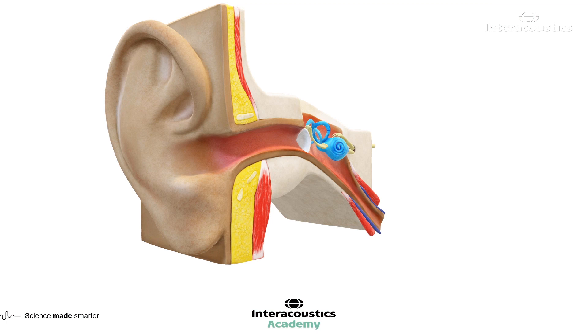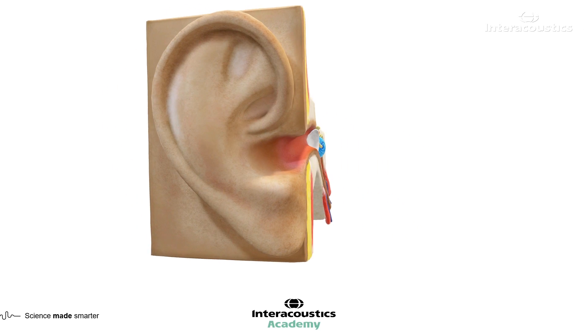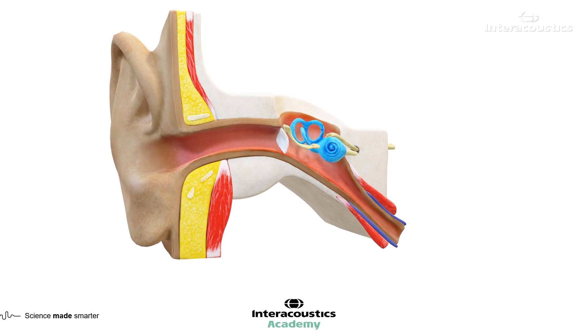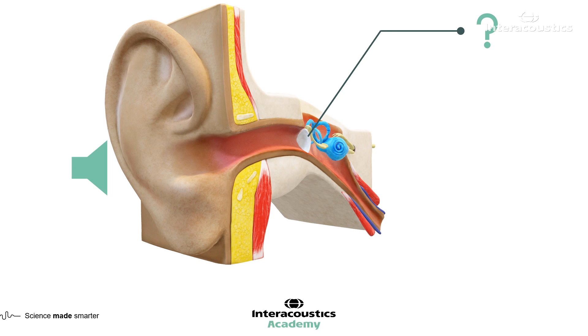One of these aspects is ear canal shape and size. Some people have much larger ear canals than others, and if we think about age, that's a significant effect. Some people might have a wider, shorter, or longer ear canal, and shape also has an impact on sound as it travels towards the eardrum. What we really need to know is the sound that reaches the eardrum, because this can vary between individuals, meaning that the sound delivered by the hearing aid is not necessarily the same as what is received at the eardrum, nor will it be the same for each person.